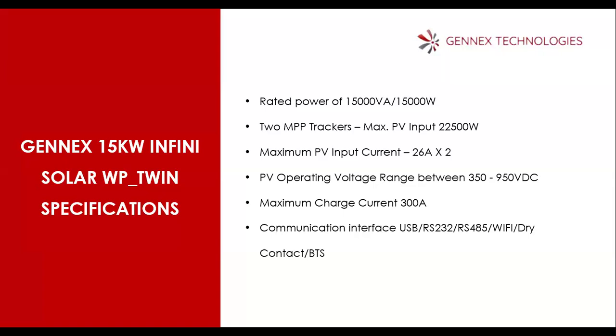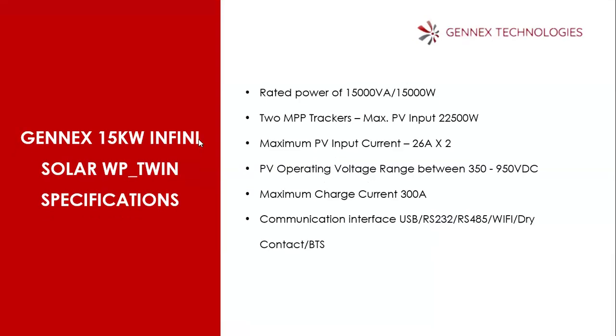That is the maximum, but you can have more than 22 kilowatts of solar panels. The only thing is that the configuration must be within the specification they give us: not beyond the 950 volts and not beyond the 26 amps of short circuit current. It will take all the solar panels conveniently and generate very well for the battery and for the load. Then the maximum charging current is 300 amps, which is massive for a 3-phase inverter.